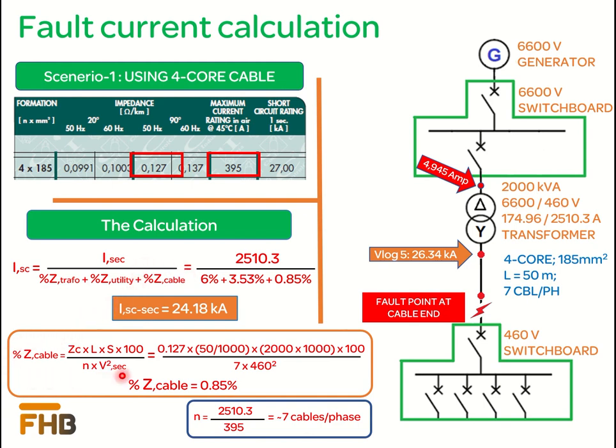In the formula, Z-C is the cable impedance and its value is from the cable datasheet, which is 0.127 ohms per kilometer. This is the corresponding value at 50 Hz frequency and 90 degrees cable end temperature.